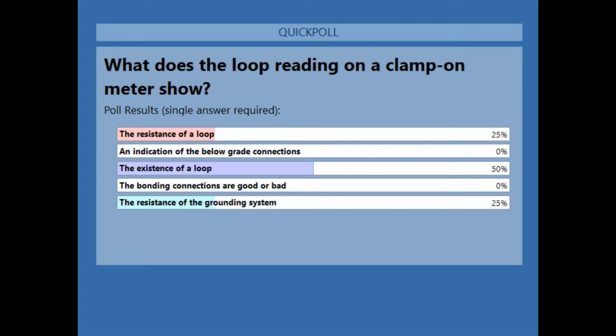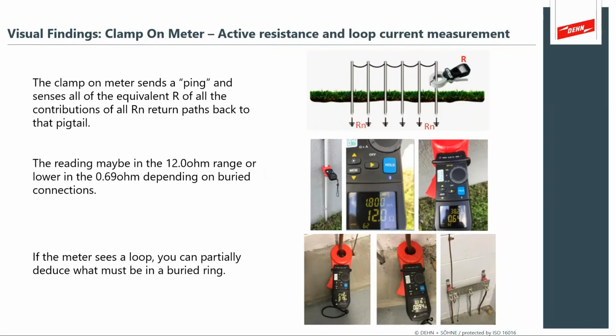So I'd like to move on and show some really important basics. A clamp-on meter looks like that top graphic. You're measuring one pigtail and you're looking for a loop. What it does is it sends out a signal, like a sonar ping, and then senses the return signal. And what it actually sees is everything relative to its contribution. So you're seeing the one pigtail loop, but it senses all of that buried resistance of these unconnected resistances through these other earth terminals. And the reading might be high, maybe in the 12 ohm range, or it might be small, depending on what's buried. But what's important to understand is it doesn't tell you the entire system.